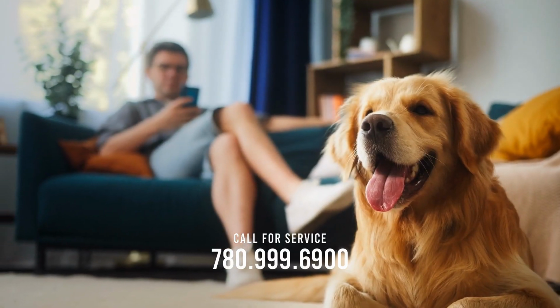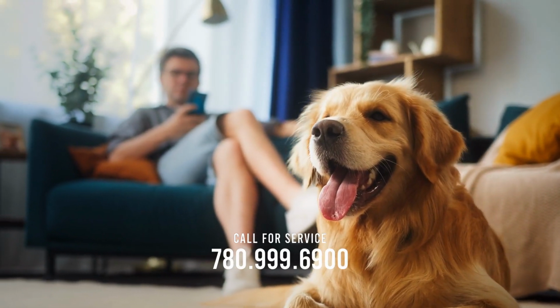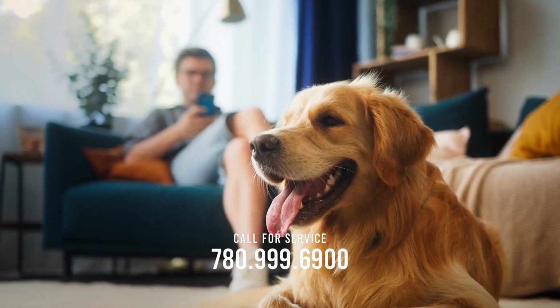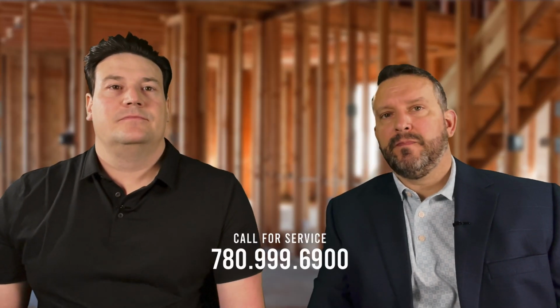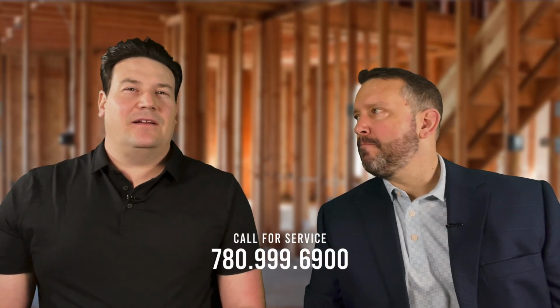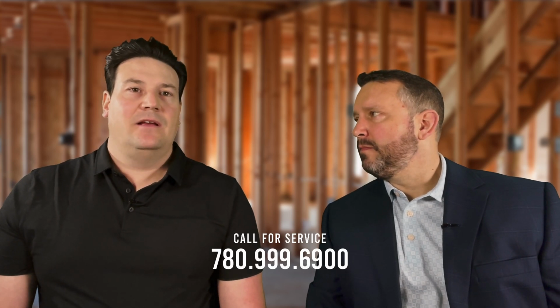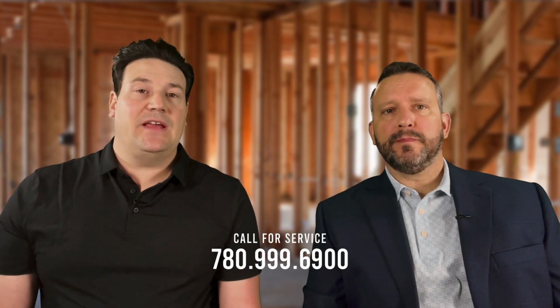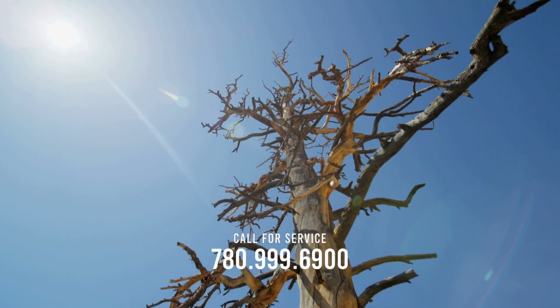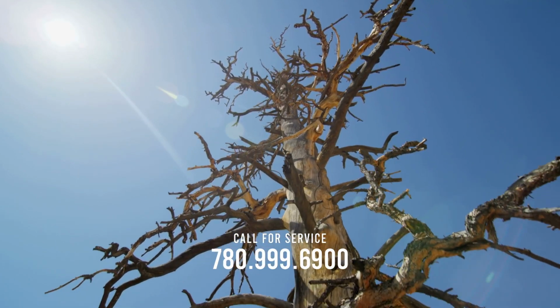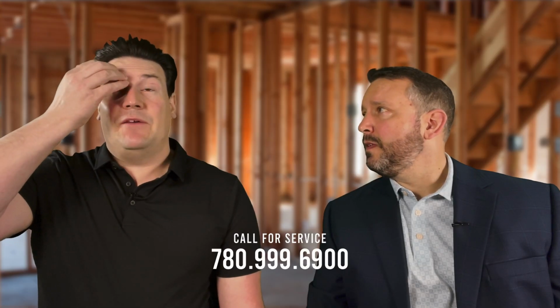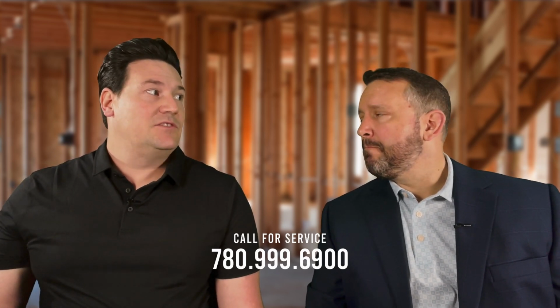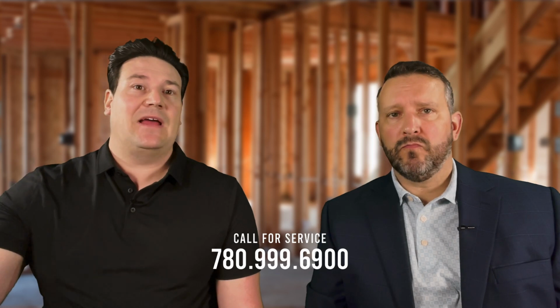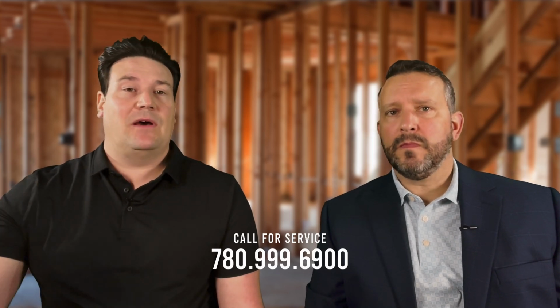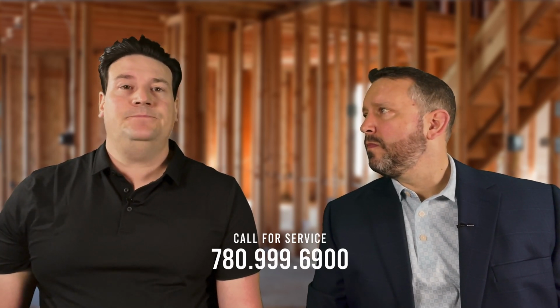Let's get into the next decision people would have: why would I choose either an ERV or HRV? It's based on the different climates we're in. You can actually use an HRV as a dehumidifier as well as bringing in that fresh air. So if your home has a high humidity level and we're in a dry climate, it can be used to dehumidify. It'll bring in that drier air and expel the moist, warm air.